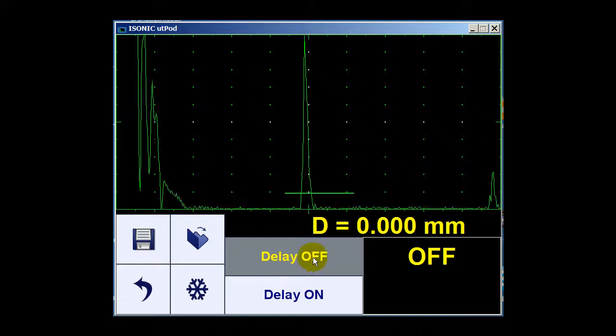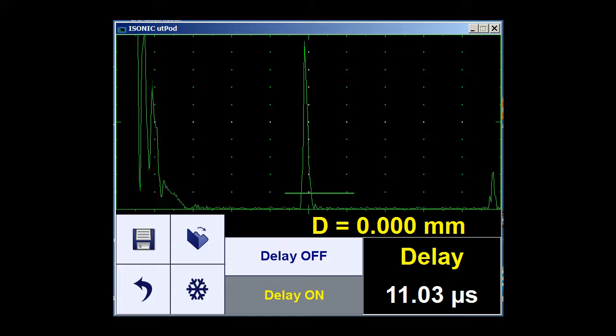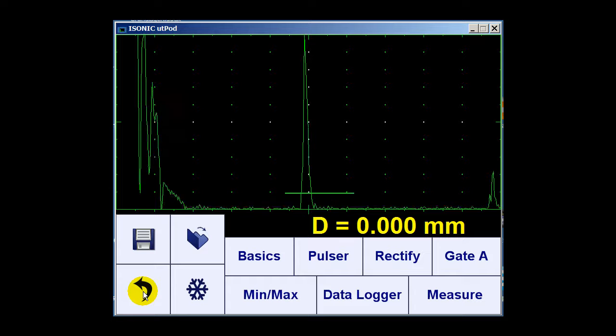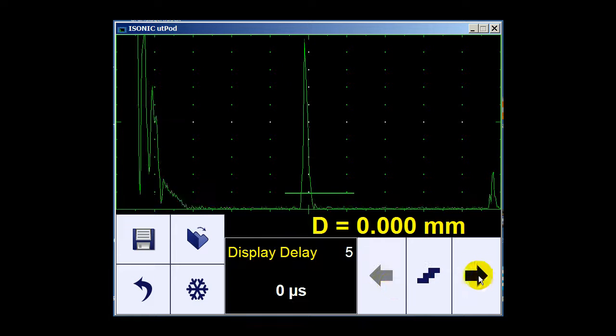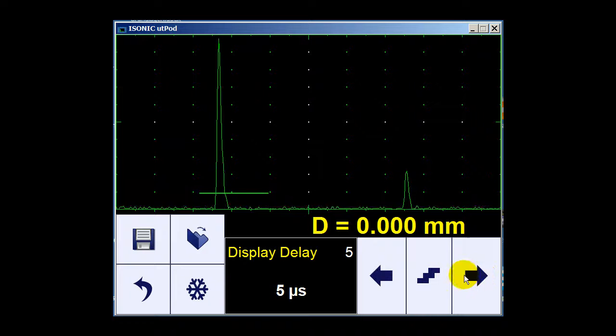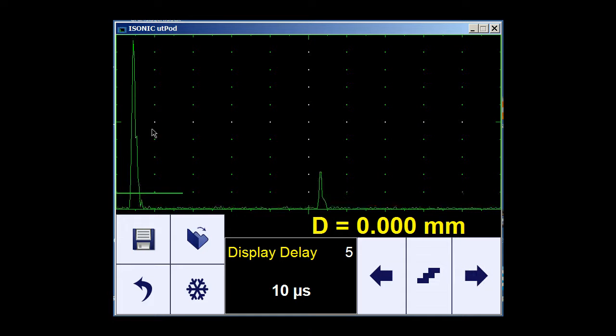After switching from delay line off to on, it measures the delay line at 11.03 microseconds. Now, in order to ease the calibration, I make sure that I move the delay line indication to the left of the screen.